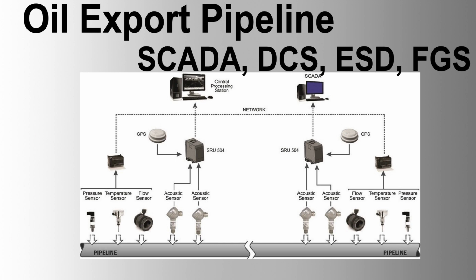3. Emergency shutdown system. Example, Siemens SIMATIC PCS 7 Safety Integrated. Hardware specifications, safety PLCs, Siemens S7-400F/FH PLCs with SIL-3 certification. I/O modules, safety I/O modules with redundant configuration for critical signals. Safety relays, redundant safety relays for executing shutdown commands. Networking, redundant PROFIBUS/PROFINET networks for reliable communication. Software specifications, safety software, Siemens SIMATIC Safety Matrix for safety logic configuration.